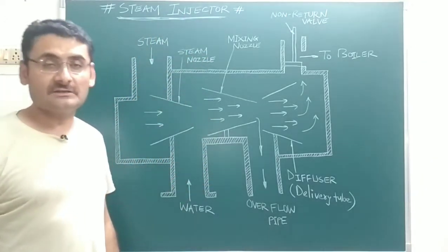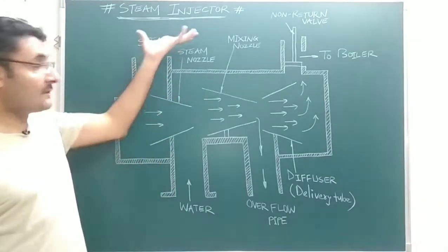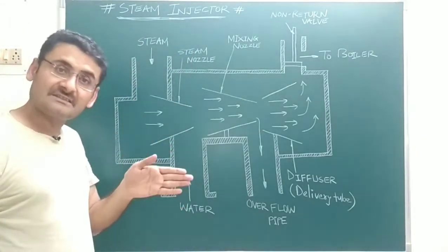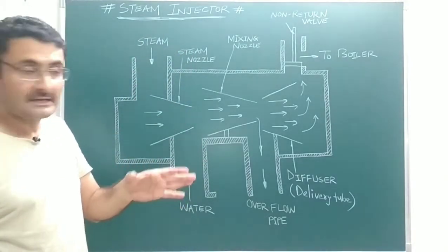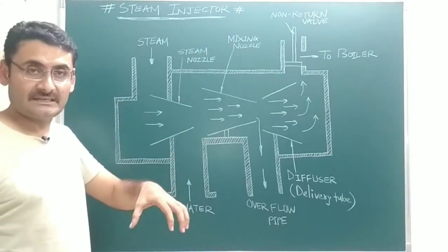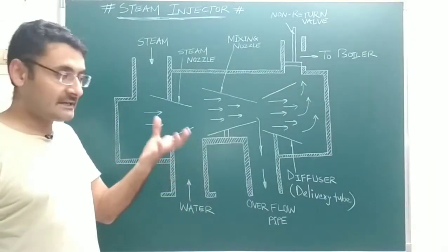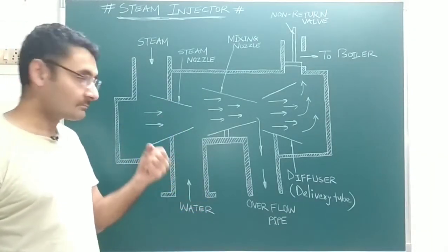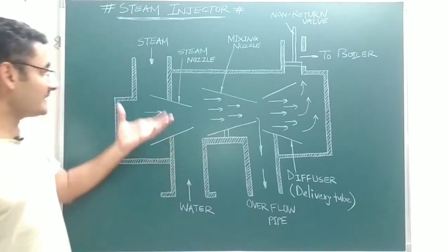Because the steam injector saves power, it increases the efficiency of the boiler. This type of steam injector is used for vertical axis boilers or locomotive boilers — both of which have low capacity. So steam injectors are applicable only when the capacity of the power plant is low.